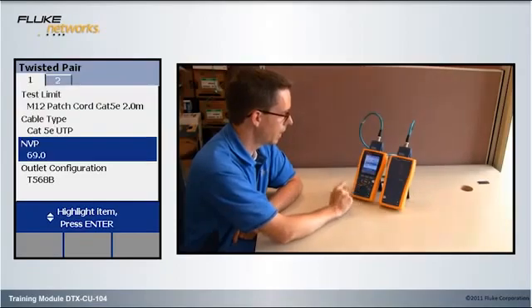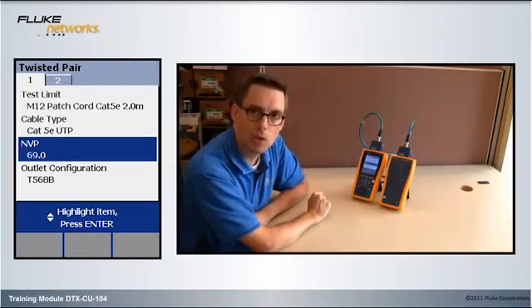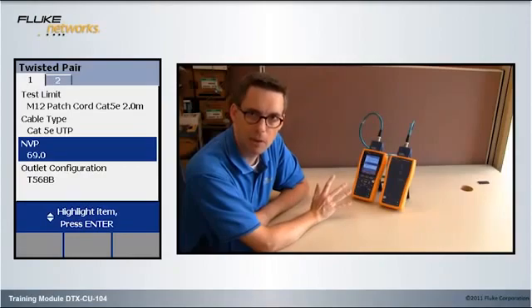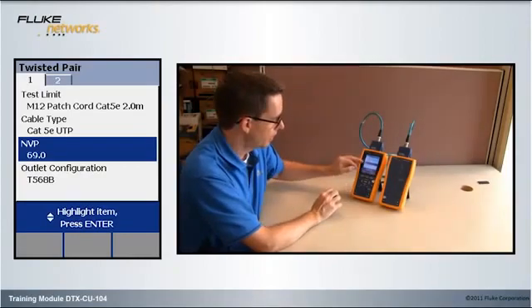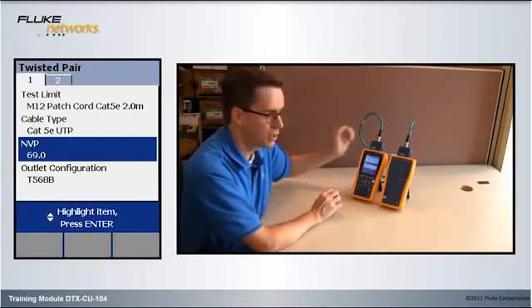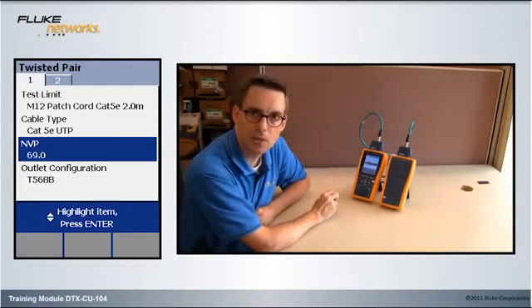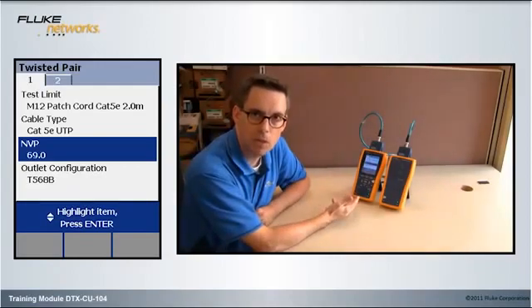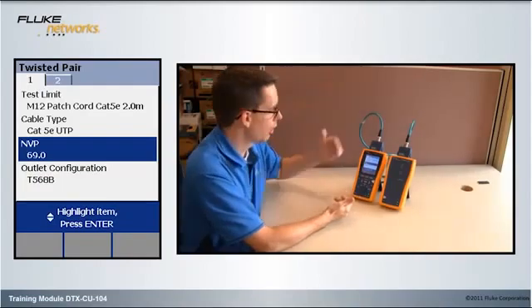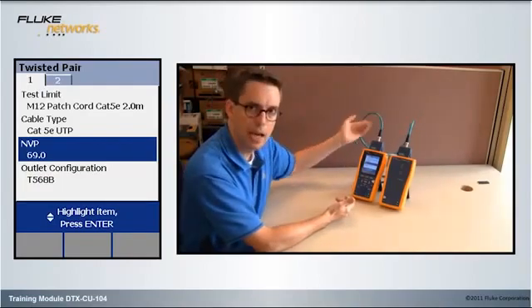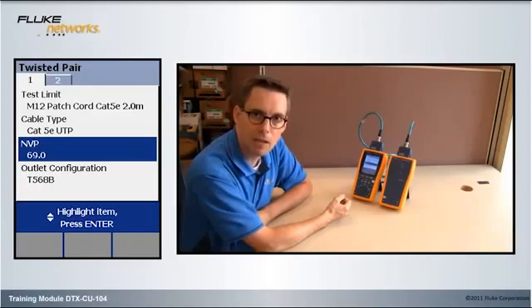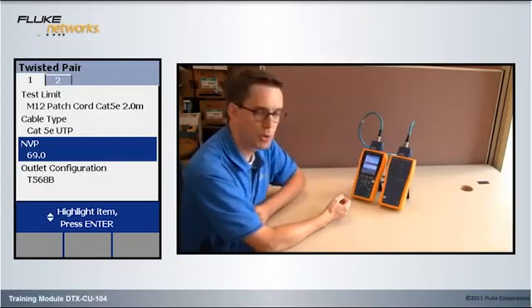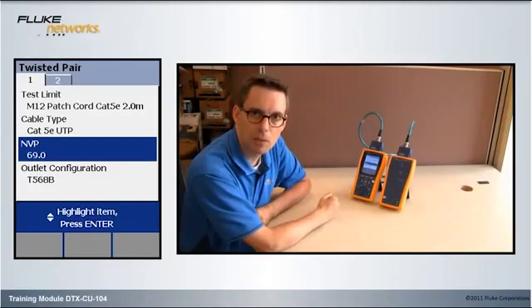Then, my NVP, the Nominal Velocity Propagation. Don't be intimidated by this. This value here will only affect the length reported by the tester, and given we're only measuring 2.1 meters, it's not that critical. However, contact the cable vendor and find out what the NVP of their cable is. Simply put the figure in here, and then your length reading is going to be spot on.